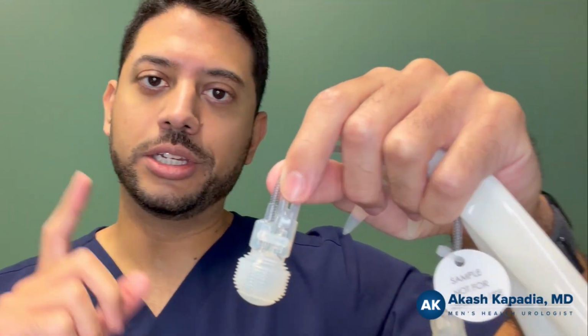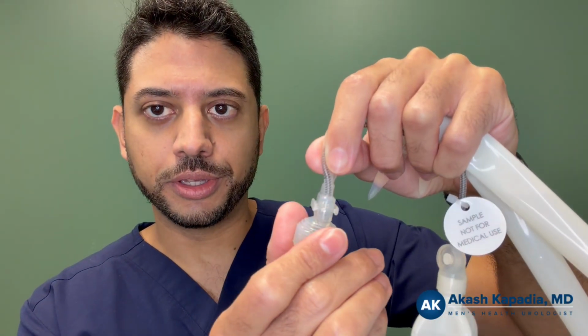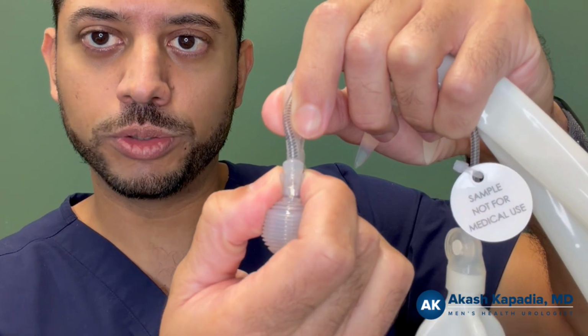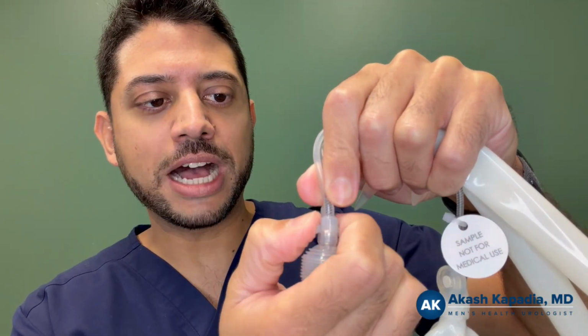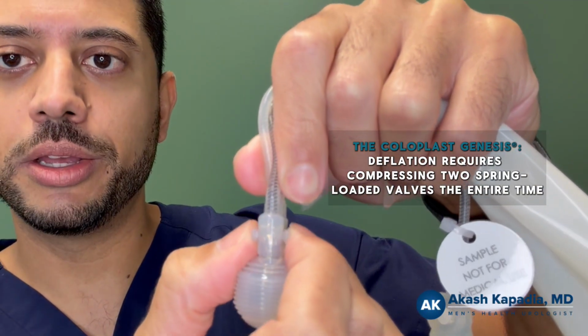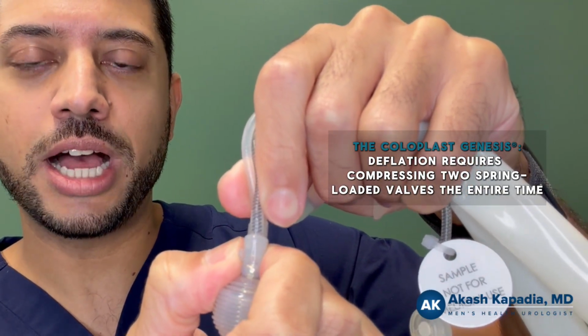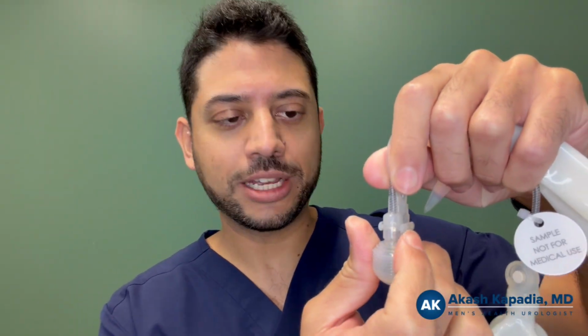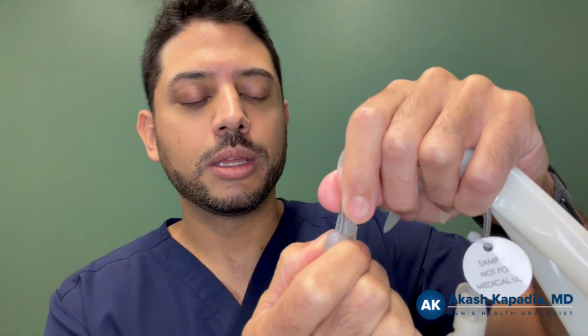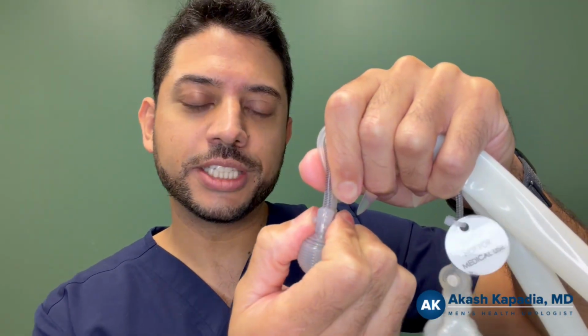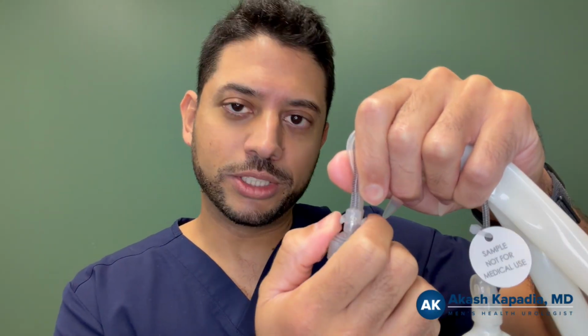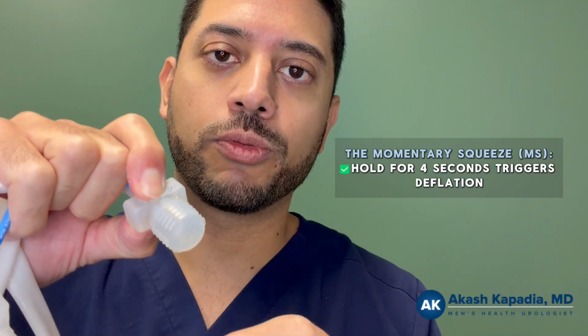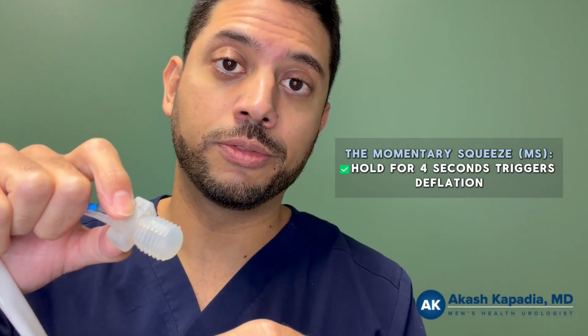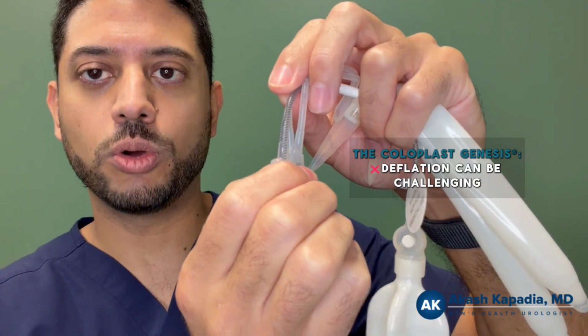Where it lags a little is on the deflate side. On this device, you have to press these bars or valves the whole time while deflating. You've got two spring-loaded valves for deflation, and compressing that valve the whole time is really critical. So while the inflation is excellent, the deflation can be a challenge for some men. Because it's a lower profile pump, it's relatively easy for men to find these deflate valves, but it's not a one-touch press and release, and I think that's one of the challenges. What I forgot to mention with the MS pump is that it's a one press, hold for 4 seconds, and release pump, which allows for auto deflation, versus this which requires compression the whole time in order to deflate.